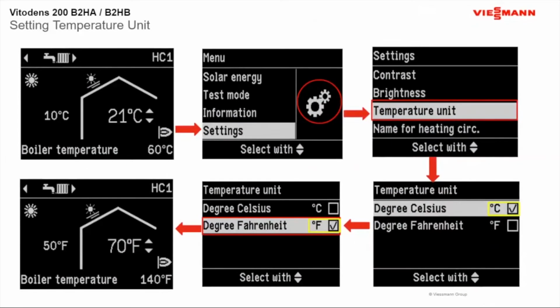Just showing you here, when you go into settings, now you can change your temperature units from Celsius to Fahrenheit. And so now you can see everything's in Fahrenheit, as well as this one here showing you a heating circuit. With heating circuits, it's showing you inside the house, that's your room temperature set point. Like in my house, I would go down to my boiler, and if I want my house to maintain 70 degrees, I would put 70 degrees here. And this is showing me what my outdoor temperature is.